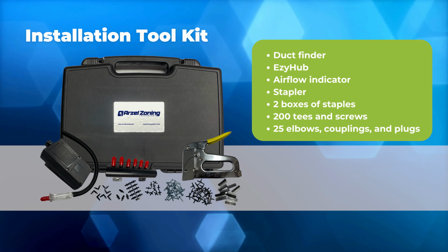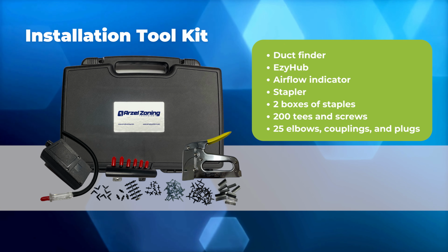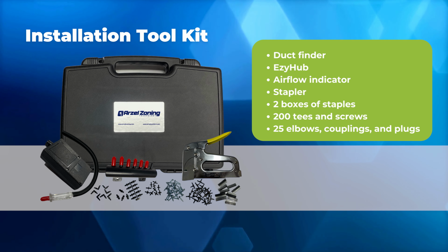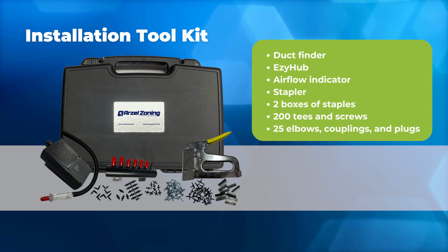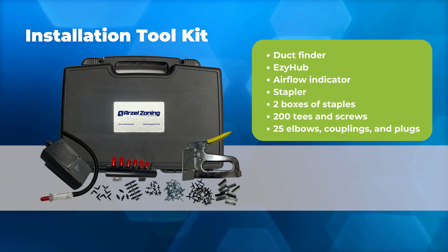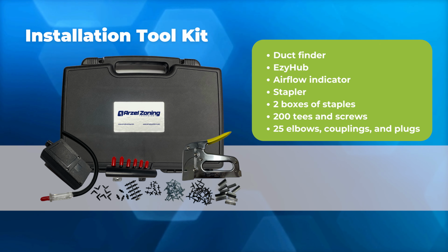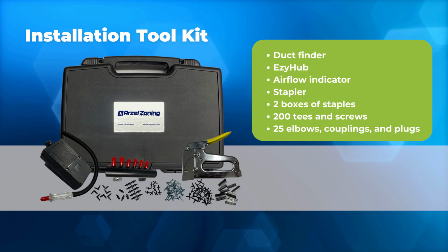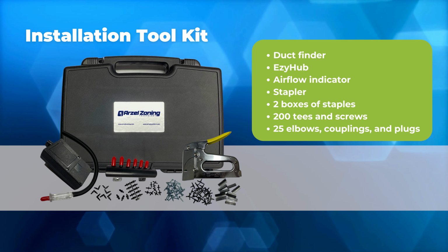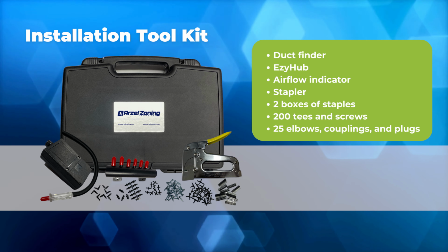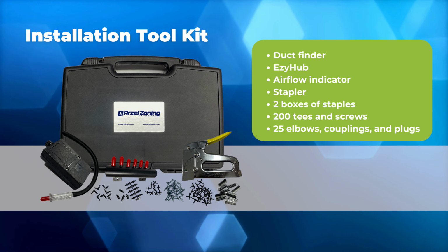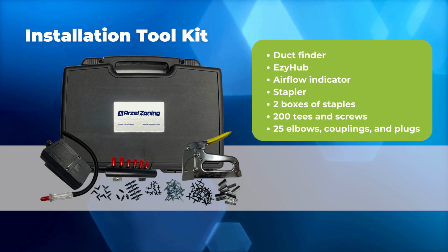Then you're going to have your stapler, which is great for the tubing itself. I also used it all the time for just thermostat wire when I was in the field as well. You're going to have 2 boxes of staples, which is, I believe, 100 staples per box, so you have 200 of those. And then it's going to come with 200 T's and screws for your installation. And then it's going to have 25 elbows, 25 couplings, and 25 plugs. So essentially everything you're going to need. If you guys do a lot of installs, I would definitely have this kit on the truck.